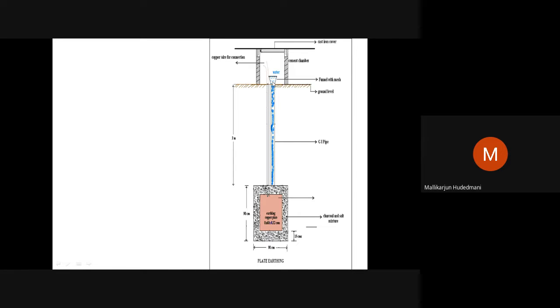The GI tube has electrical contact with the household meter wire. This way a pipe to plate conversion comes. Here it is a plate, and the GI tube gets connected to the plate earthing. So throughout the periphery of this, around 15 centimeters, you bury the charcoal and salt and complete it.